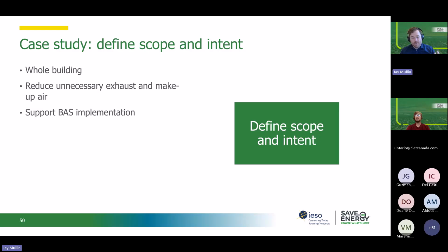So when they defined that scope and the intent, they wanted to cover the whole building. One of their goals was to reduce unnecessary exhaust and makeup air to address those potential safety risks and also to save energy and reduce natural gas, because they know they were using a lot of that. They saw that opportunity. The other intent of this study was to support their BAS implementation. So they knew that for the BAS, they were going to have to do that equipment inventory, map things out, and figure out how things should be controlled. And they saw this air balance study as being really useful to inform and facilitate the BAS implementation.